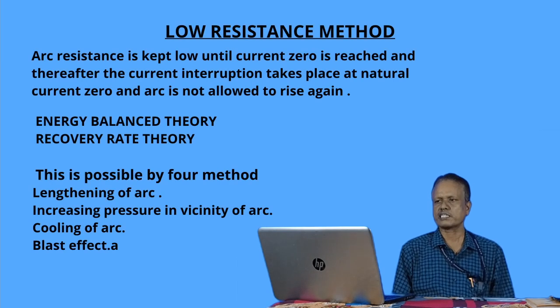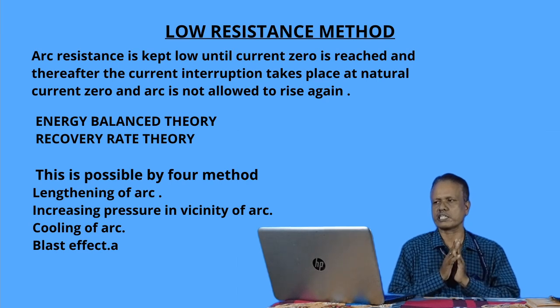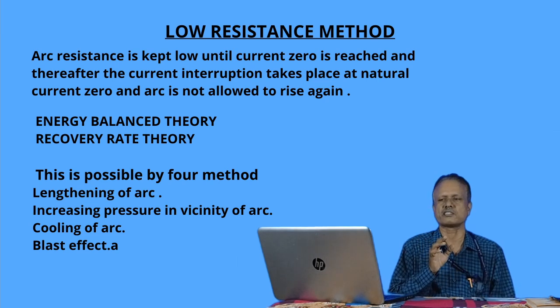Next, low resistance method of arc extinction. Arc resistance is kept low until current zero is reached, and thereafter the current interruption takes place at natural current zero and the arc is not allowed to rise again. This is achieved by increasing the length of this arc, increasing pressure in the vicinity of the arc, cooling of this arc and blast effect.